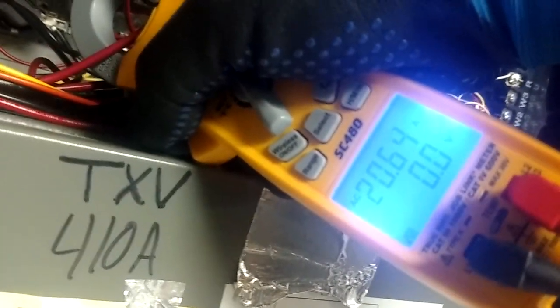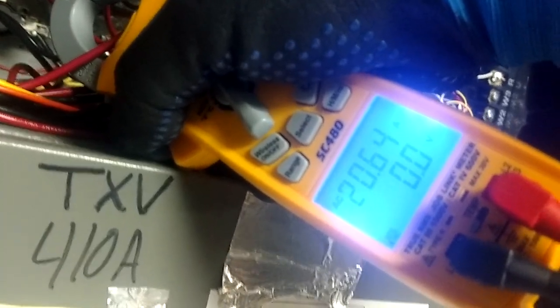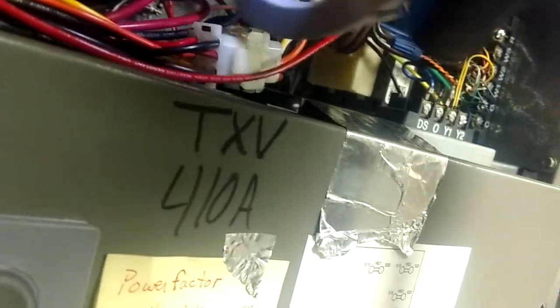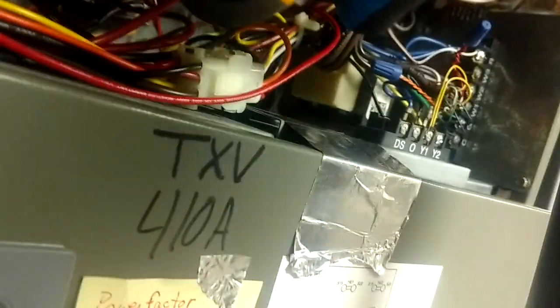And then if we check our individual wires, see how well that light lights everything up, we are going to have 20.6 there. And then we have another one right here, and you can see 21.4. So our amp draw has verified that our heaters are on.